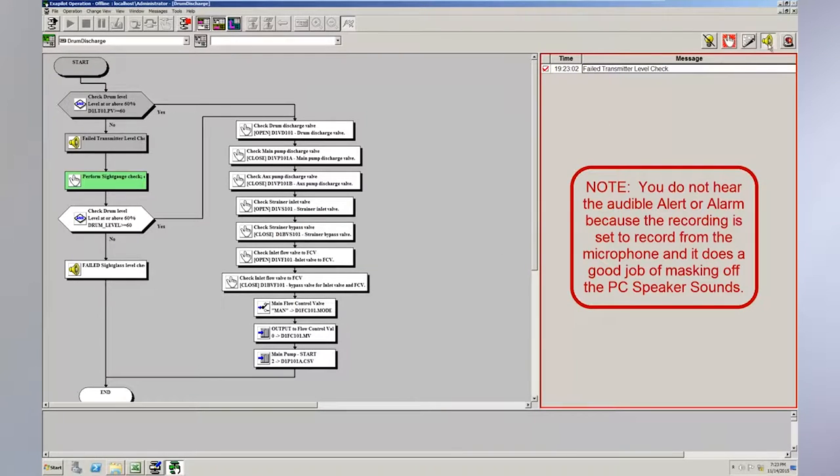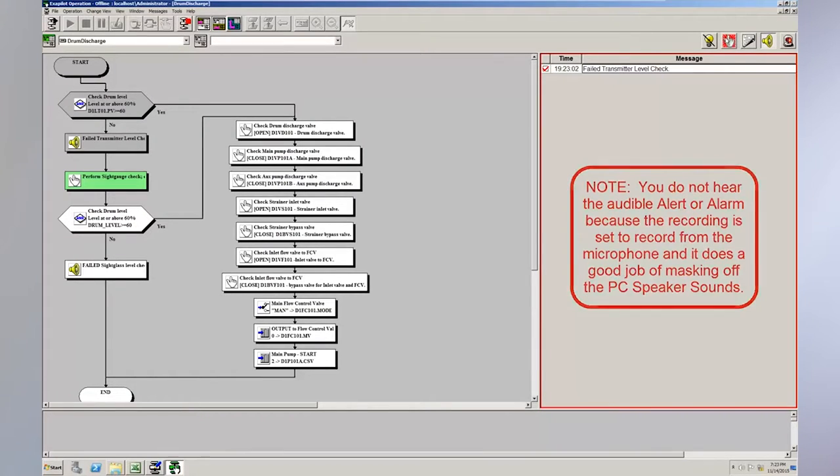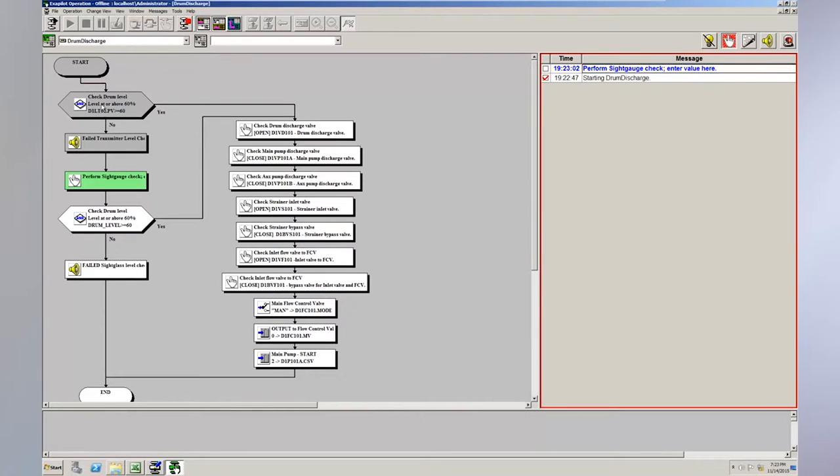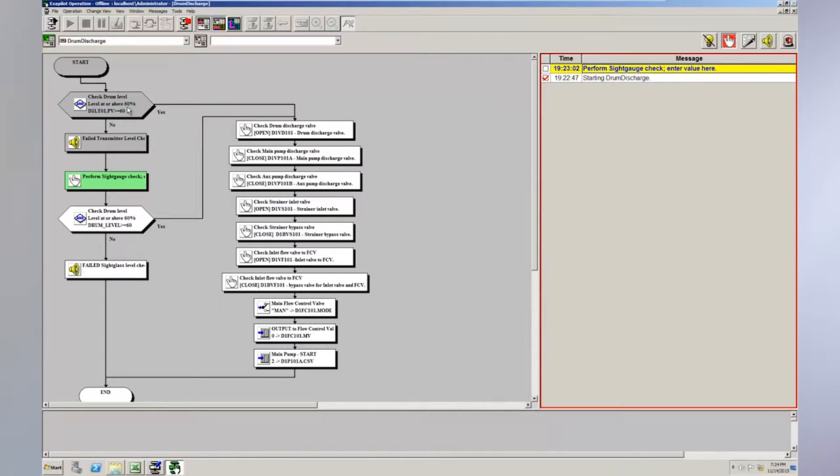So what I did here was an alarm went off. So I selected the little alarm icon to bring up the alarm message list. And we see that I had a failed transmitter level check. And I selected OK. That silenced the alarm. Let us know the operator can view that. And you still see that we have a remaining operator message waiting for us. And this is to perform a sight gauge check because the transmitter check failed. So everywhere you see this gray, that's the procedure steps that have already been executed by the procedure. The green procedure step is where the procedure is still on. That's the step that the procedure is still on. And where it's white, none of these have been executed yet. So you can see that we already went through. It automatically read in the level. And it didn't meet the 60% criteria. And then we got the failed transmitter level check alarm.